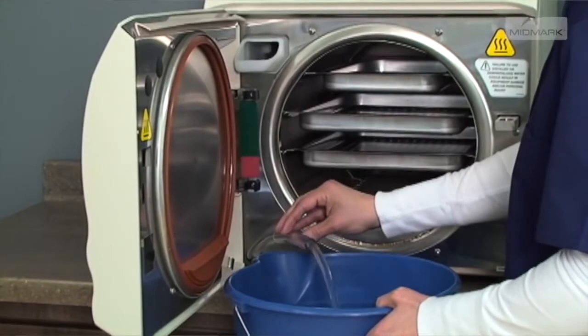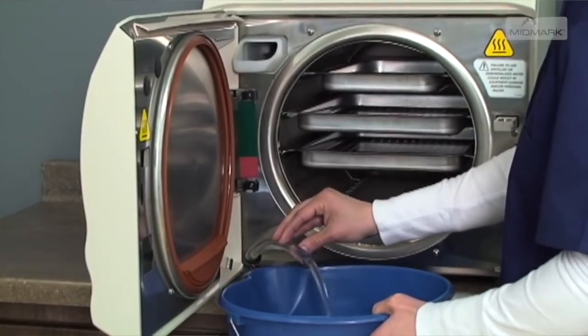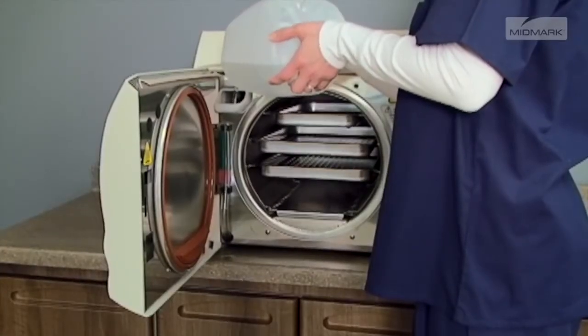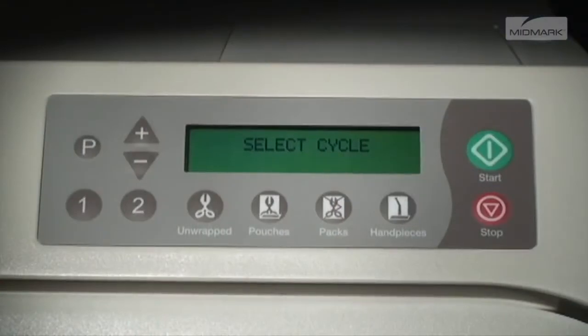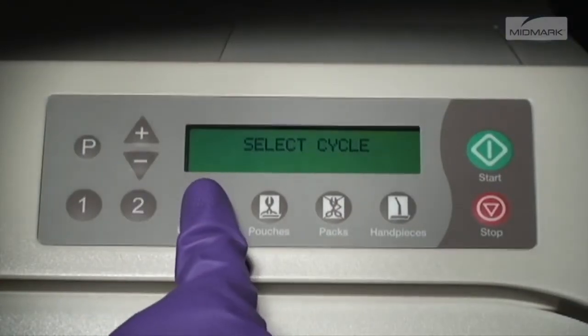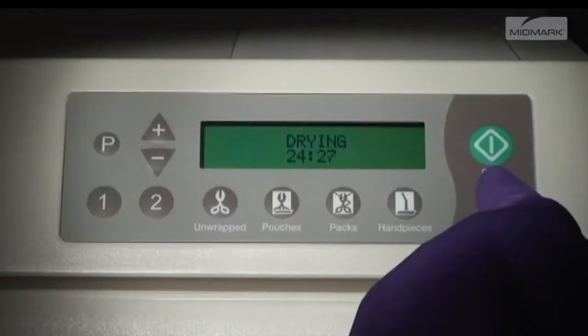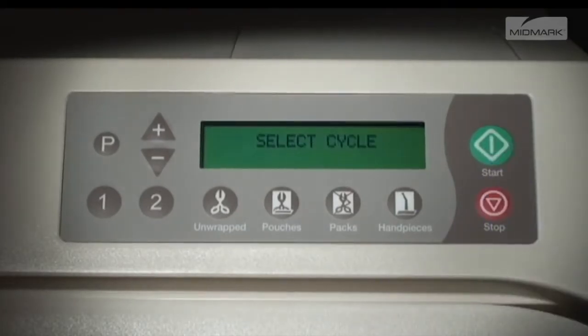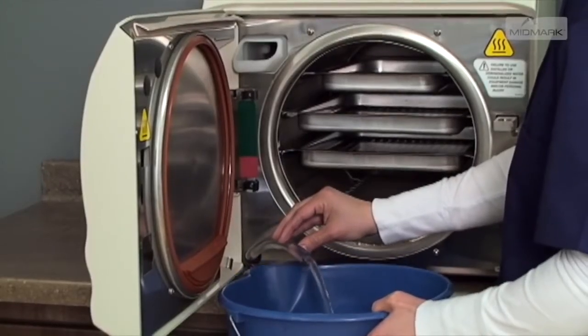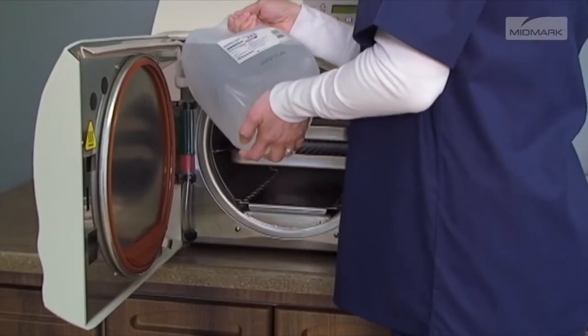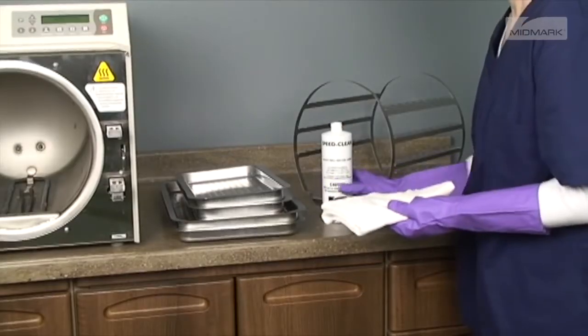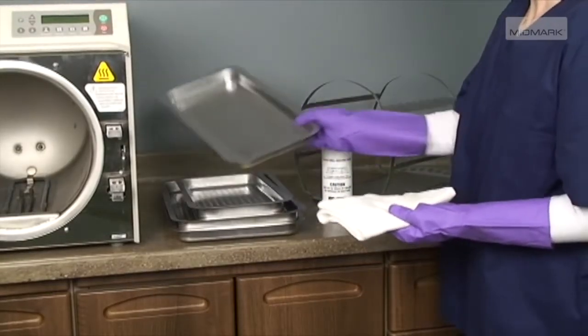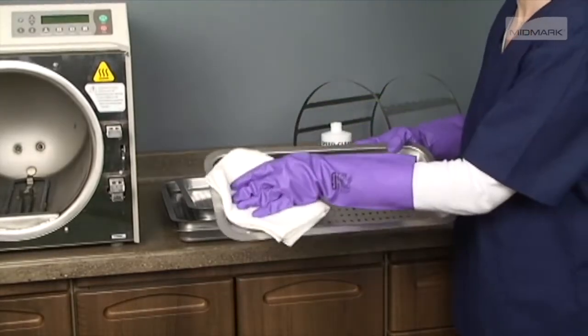Drain the reservoir again and refill a second time with clean, distilled water for the rinse cycle. Rinse by running 1 unwrapped cycle. Push the stop button when the drying cycle begins. After the cycle has completed, drain and fill the reservoir with clean distilled water, then allow the sterilizer to cool. Remove the trays and tray rack and wipe with a damp cloth.